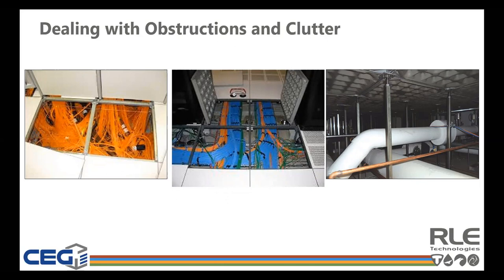But the cooling improvements gained from the project paid for itself in both the ability to increase total cooling capacity and therefore increase IT densities in that same space. And when taking all of that into consideration, the payback for the project was projected to be less than 2 years. So even in existing legacy spaces, steps like this can be taken with relatively short project paybacks.